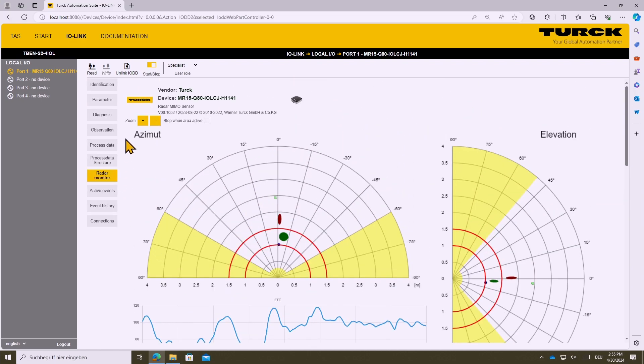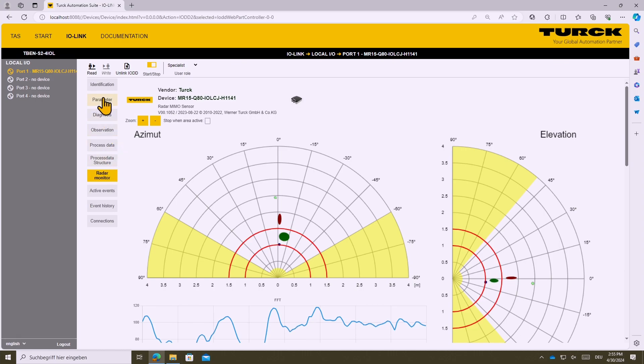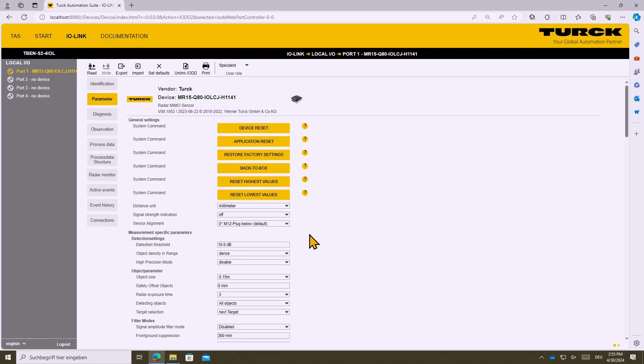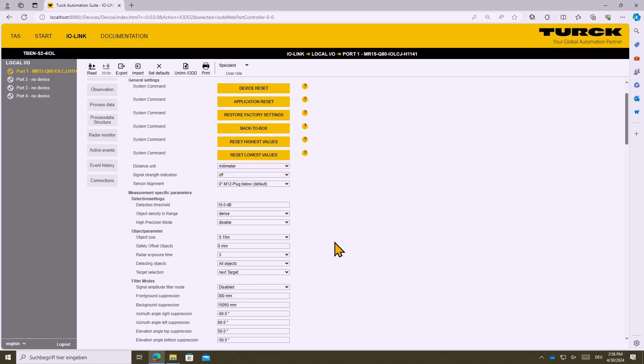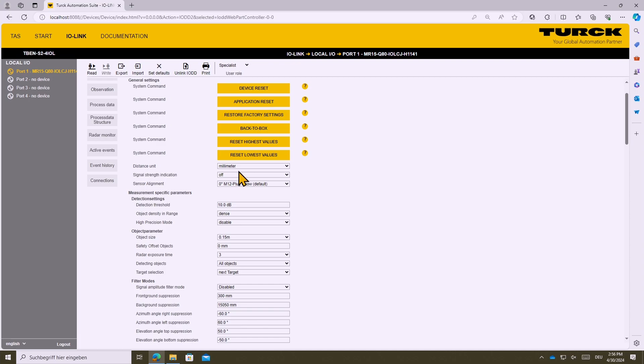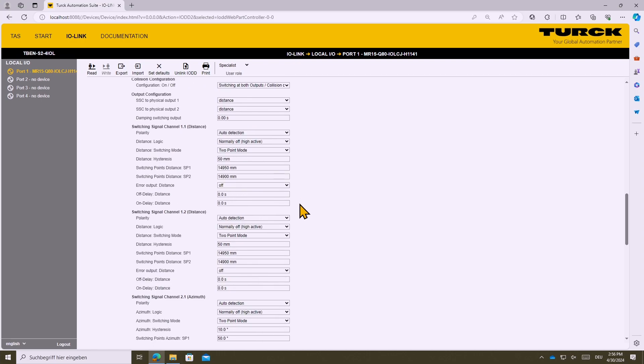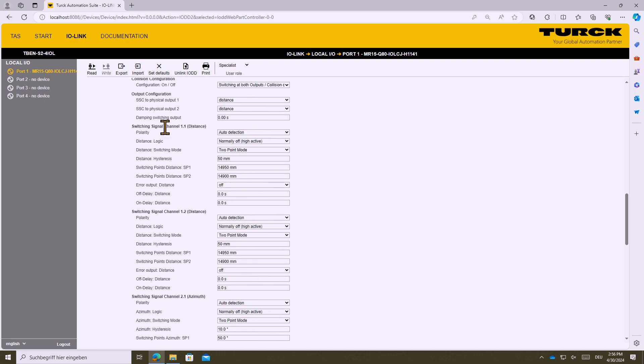But of course by changing from radar monitor to the parameter tab you can set up also all these already mentioned parameters but also other ones like for example changing the detection unit, changing the orientation, the mounting orientation of the device. But also changing all the switching behavior like it is defined in the smart sensor profile.